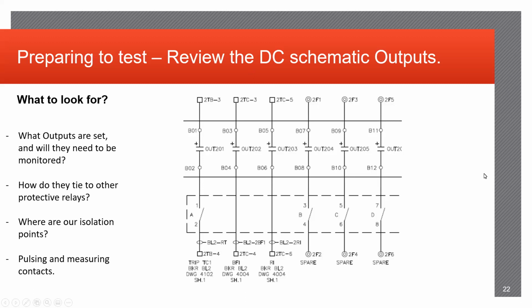If there's any protection logic associated with that output contact, you'll usually run that test first, identify that it works as design intent, and then later identify that the output closes when that protection logic goes through. So correctly setting up your test points from the output side of the relay to the input side of your test set is important as well, because that way the software identifies that the output did in fact pick up when need be, especially when you're getting into such finicky tests where you're verifying operations at like nanoseconds. So yeah, it's very important to identify those to begin with.